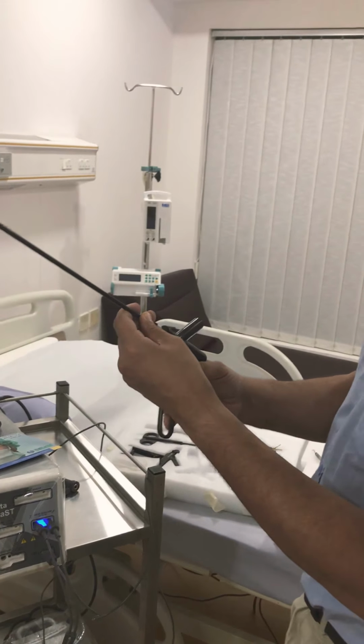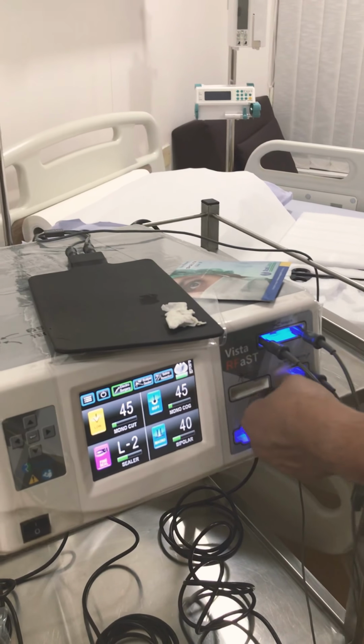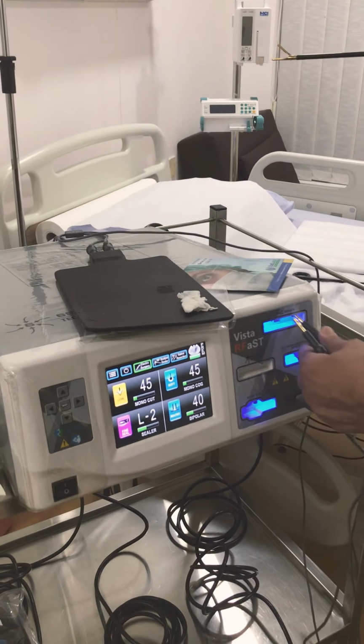So we can demonstrate here the foot switch, and this is the third foot switch we are going to use for sealer. And you can see here, this one is going to lighten here when we use sealing. Okay, it's just because this is a seal. So that's the sealer. It's a continuous energy which is different from the RF. Okay, and the bipolar goes here. This is the bipolar. The bipolar works here. So that's the foot switch of the bipolar, okay, and you can hear it here, and the smoke is coming.